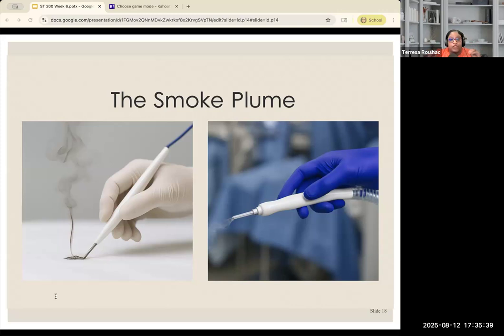Now, the chapter wants you to know the smoke evacuation system removes smoke directly at the surgical site at 100 to 150 feet per minute, or 30 to 46 meters a minute. It passes the smoke through a HEPA filter, and the absorbers trap the hazardous particles and chemicals. When they're done, these filters are biohazardous waste and have to be disposed of per hospital policy.